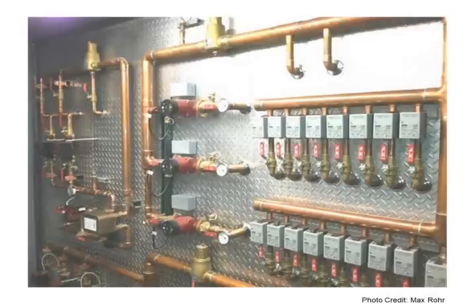Looking down below here, I can see a flat plate heat exchanger. I don't know, my guess is this is a snow melt system. And perhaps on the loop side of the snow melt system, because we're in cold weather when you have snow melt, you want to use antifreeze. So perhaps the contractor used a propylene glycol type antifreeze with inhibitors. What if he mixed with that, instead of having conditioned water, straight up well water? What are the problems and implications of doing so?